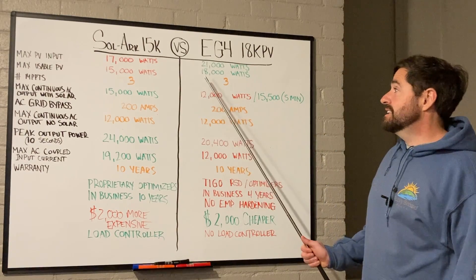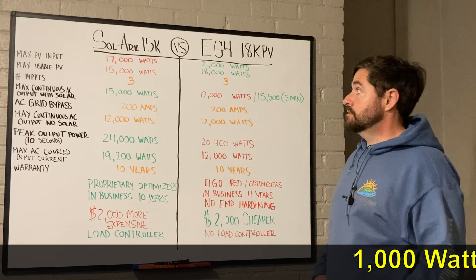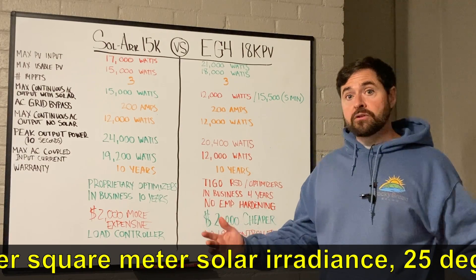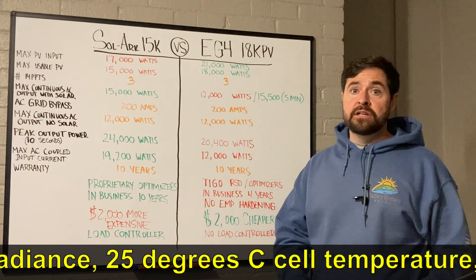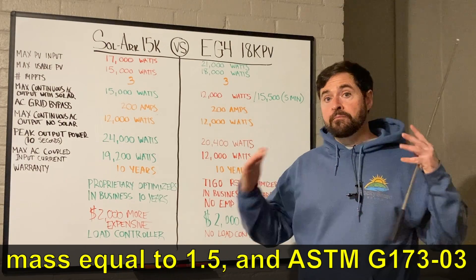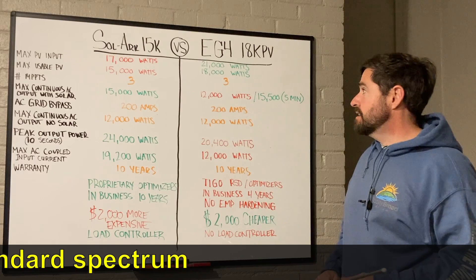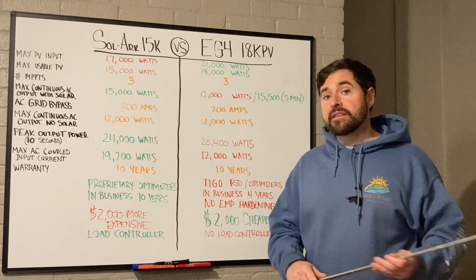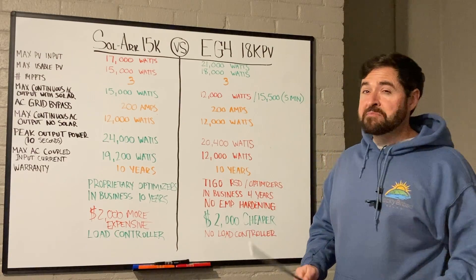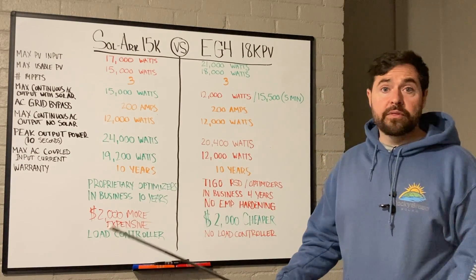Even though this inverter can only output 12,000 watts AC, it can simultaneously send the other 6,000 watts to the battery bank to charge the batteries — that's where the 18K PV name comes from, and it's higher than the Sol-Ark's 15,000-watt max PV. Standard test conditions — all panels facing one direction, perfect sun, perfect temperatures — are rare. With multiple roof pitches or different-facing arrays, you could install 17,000 to 21,000 watts of panels and rarely hit those peak numbers. Buying extra panels often isn't that expensive in the long run.